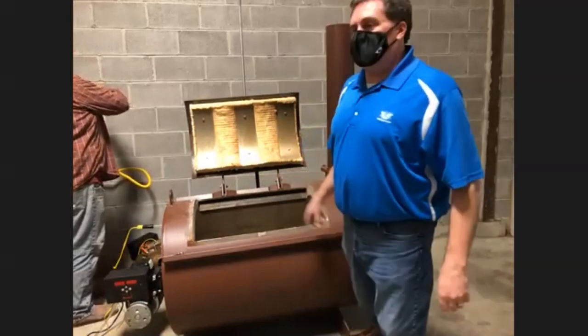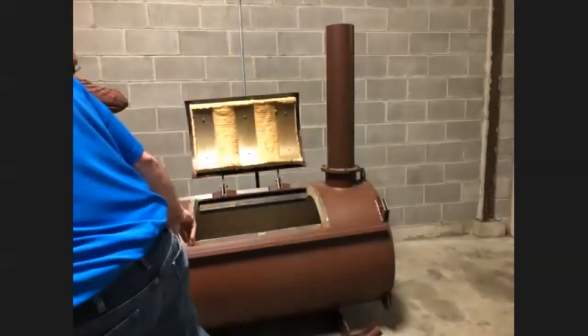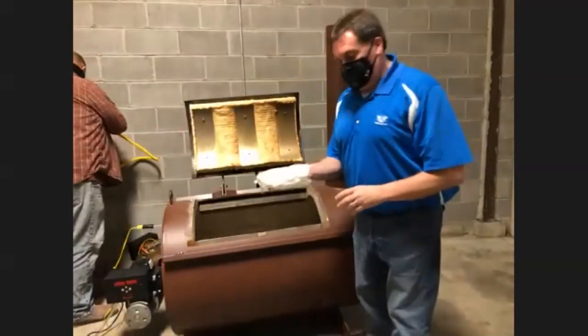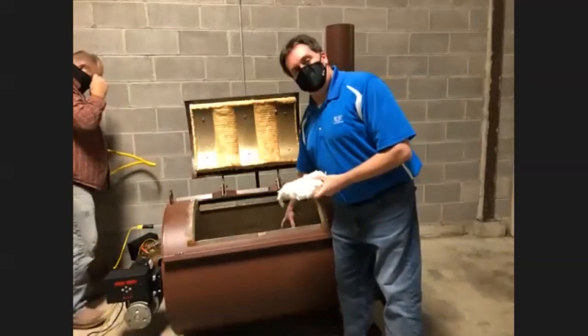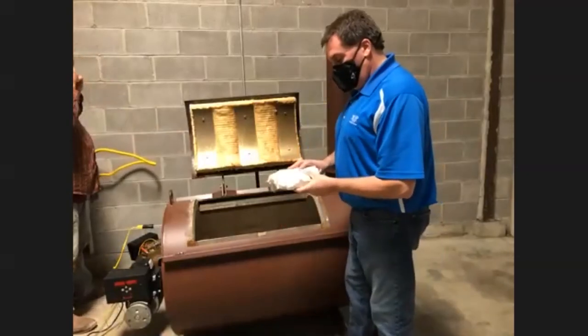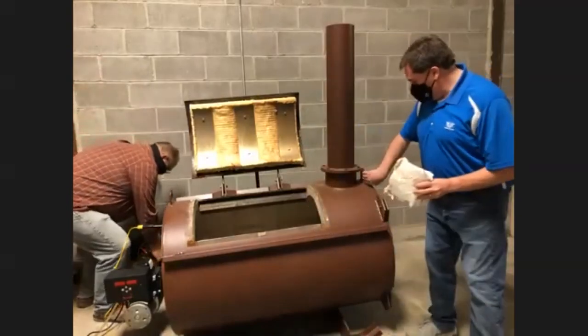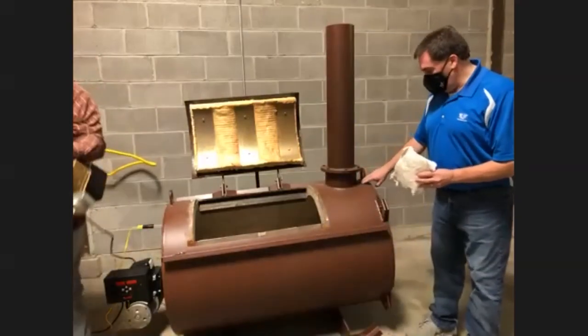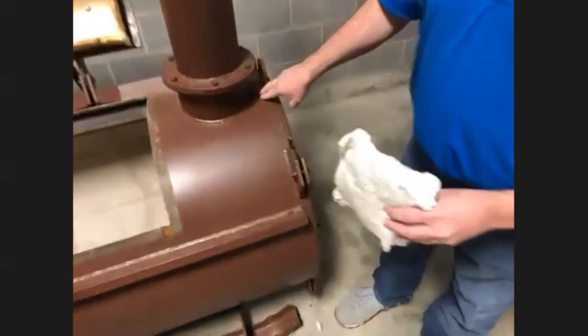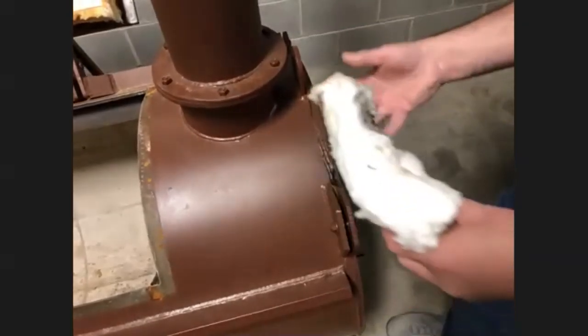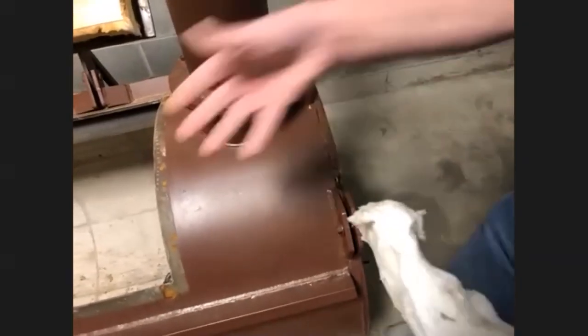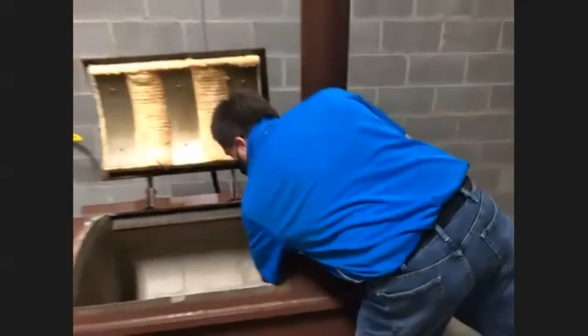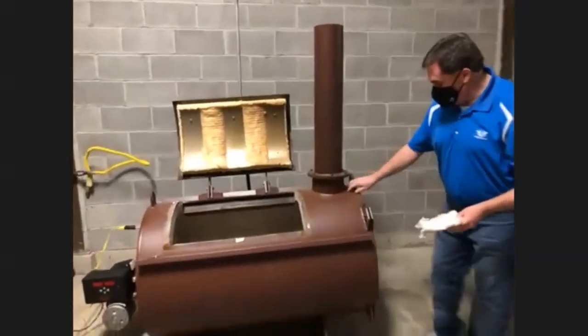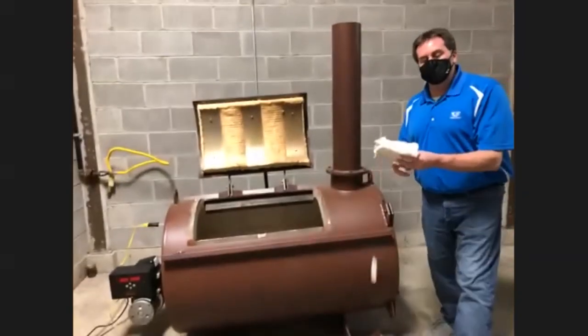When the units are shipped, there is a separate piece of insulation shipped with them. It is inside this unit, and you must use it. There's a little section right next to the stack, here on the inside, that you want to fill in with this insulation. During shipping they don't install it because it may drop out, so they just let it lay in there. You must fill in that gap, that open area underneath the shell, right here on the end, with that secondary piece of insulation.